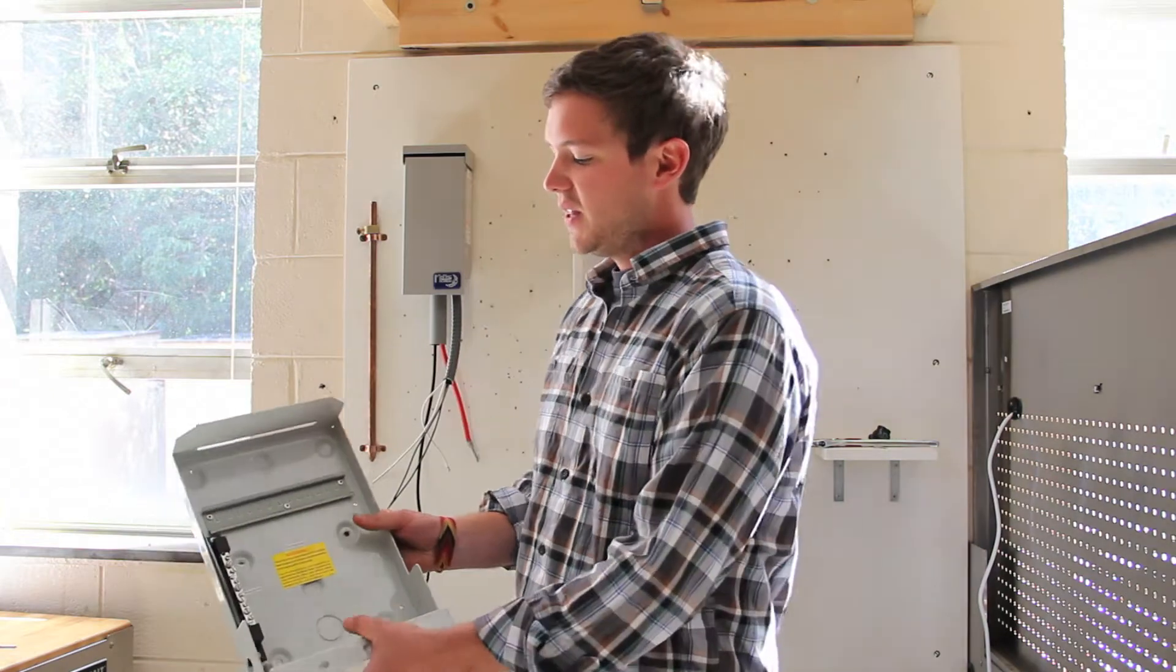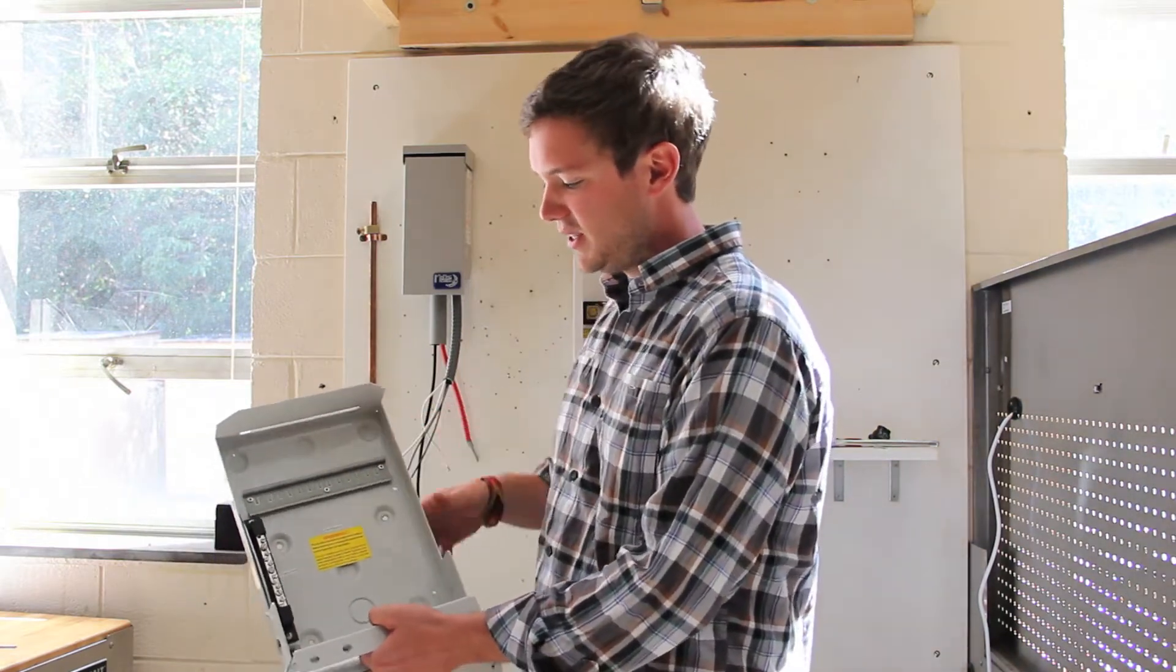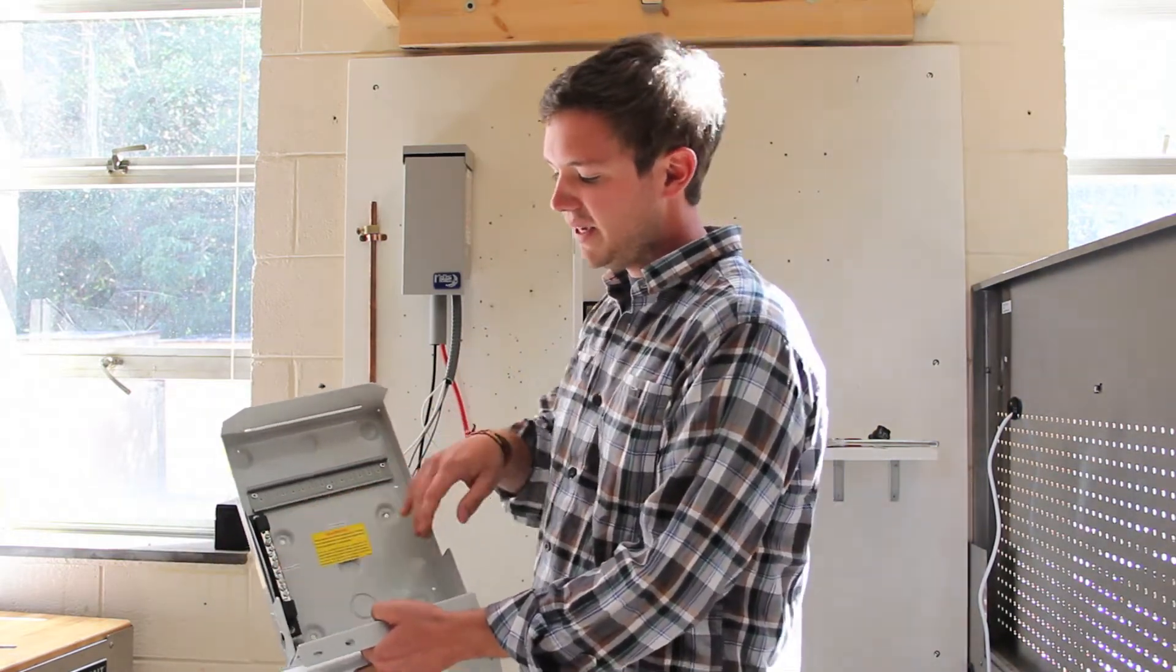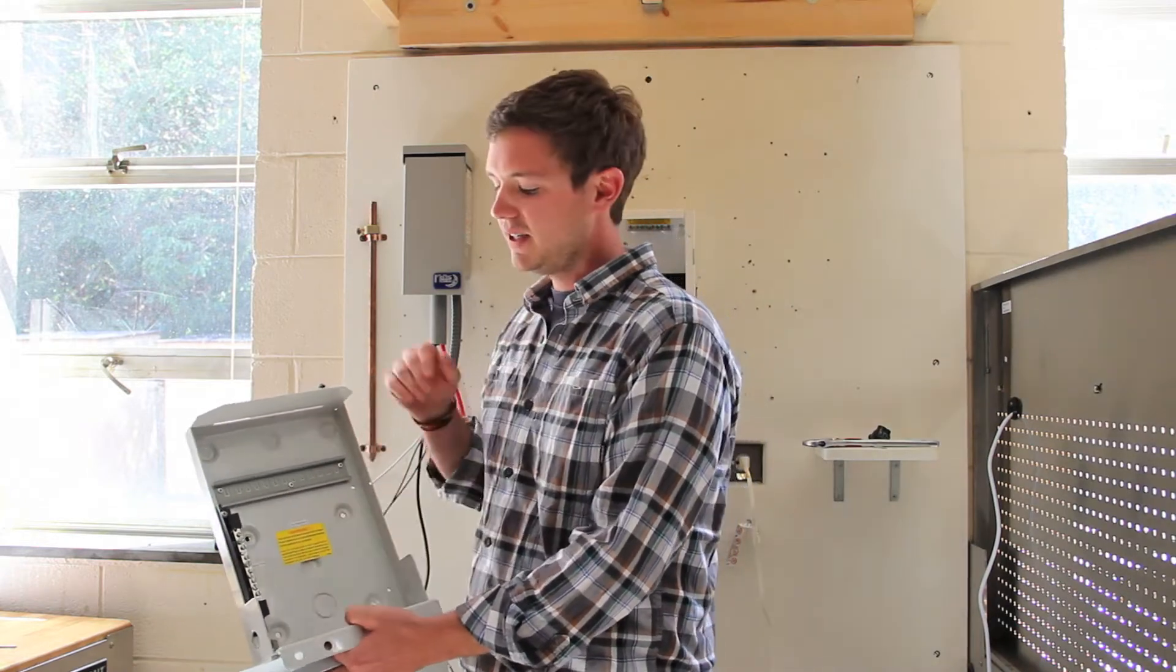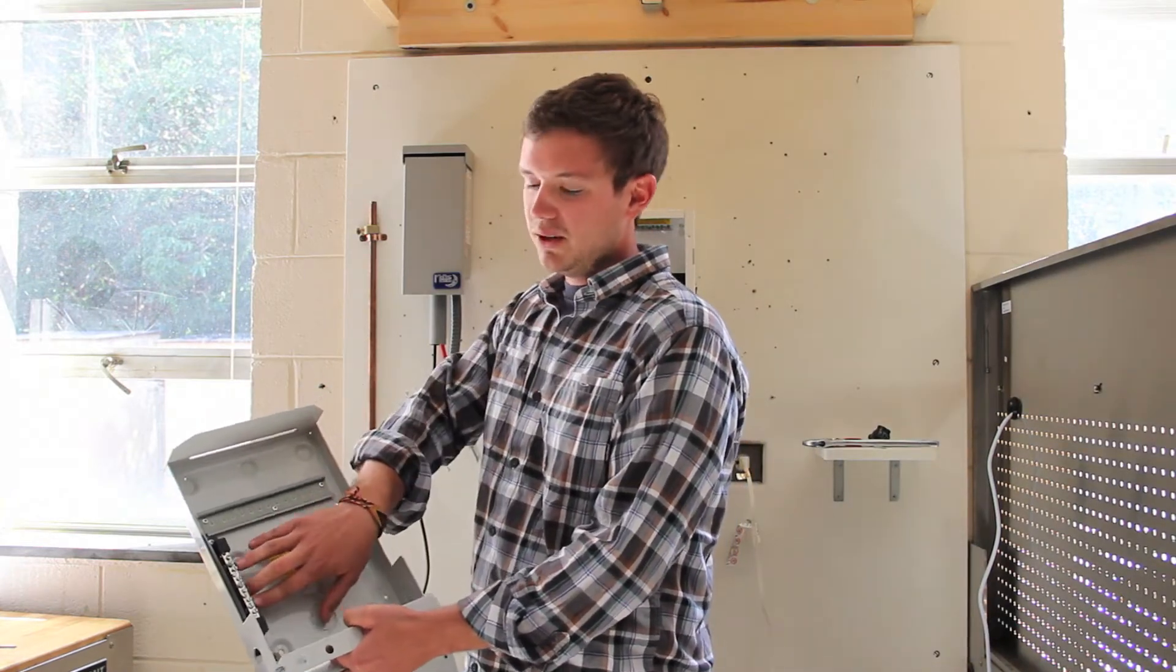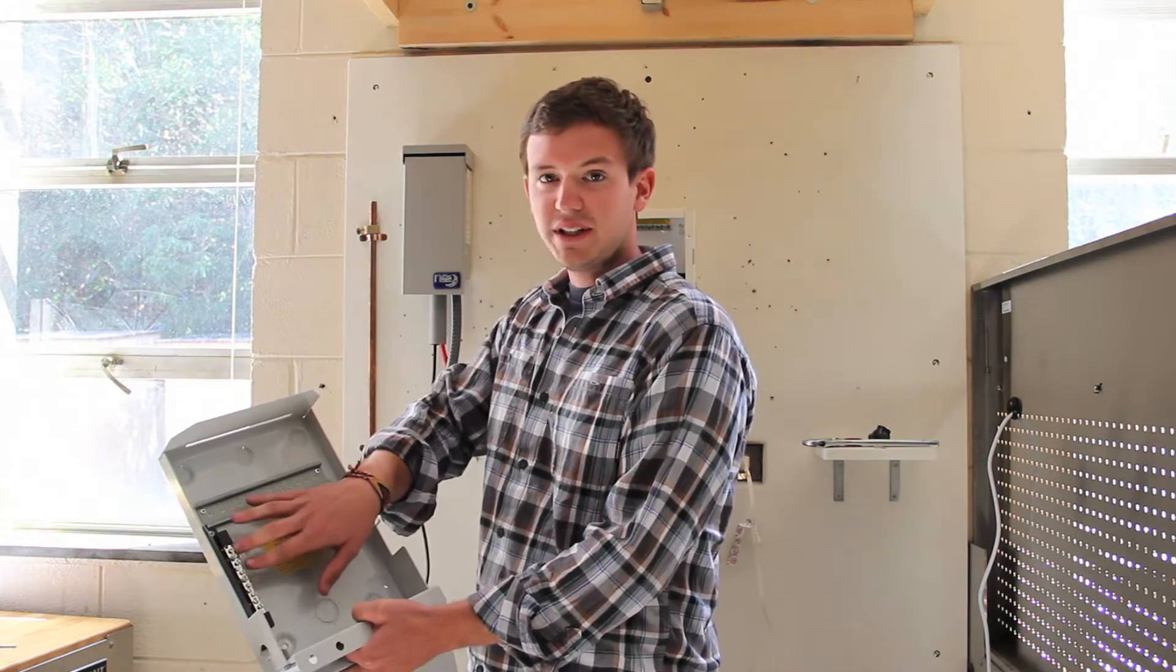In a grid tie application, you'll experience voltages up to 600 volts DC. Those mount on a DIN rail such as this. We have our PV negative bus bar and our ground lug to be able to parallel all of our strings together on the negative side.